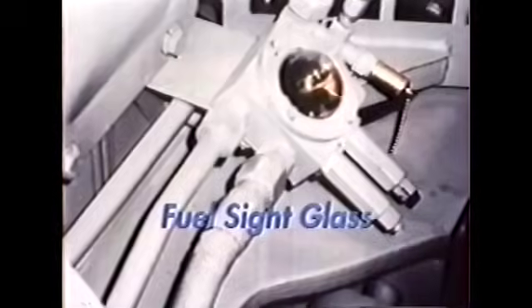Behind this door, you will find the start switch, gauges, lay shaft lever, and fuel sight glass. When starting the Dash 8, the start switch must be turned to the prime position. Examine the fuel sight glass. Make sure that it does not contain air bubbles. When the fuel pressure reaches about 45 psi, turn the switch to the start position. Hold the switch in this position.